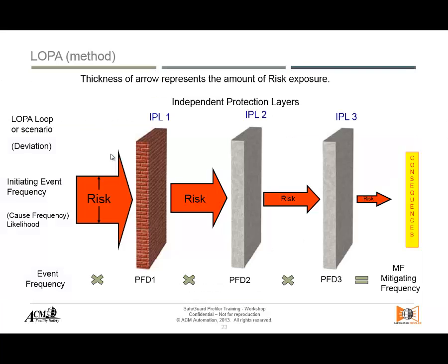Coming from the hazard analysis, the team will have already identified hazard scenarios. A hazard scenario starts with a deviation caused by a piece of equipment failing or an operator making a mistake. These will happen at certain frequencies or likelihoods over time — that's what we put in as our first factor in the equation to find our total mitigated frequency. If that event frequency is too high, the question becomes: too high with respect to what? With respect to a tolerable frequency.